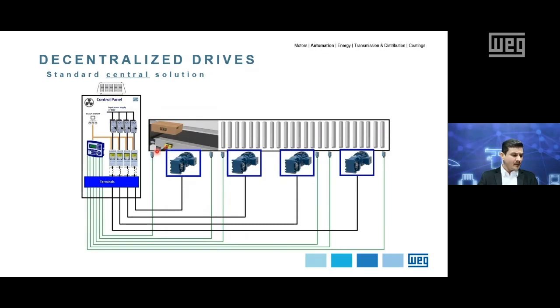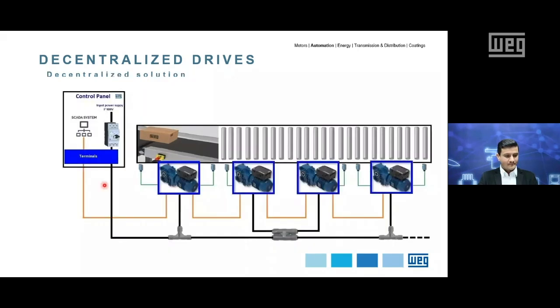panel. Further to this, as you can see in this type of installation, all the sensors, analog and digital, are going to the control panel to be read. So again, more cables are required for this kind of central topology. When we talk about the decentralized solution, now we can see a cleaner installation concept. So we have only the power and the bus cable going to the VSD.